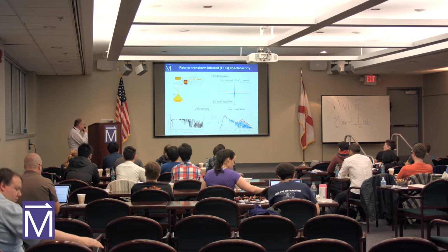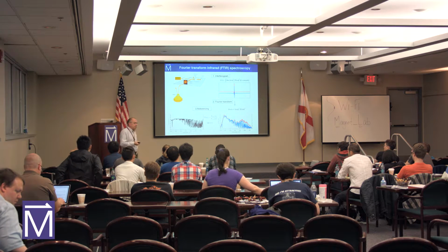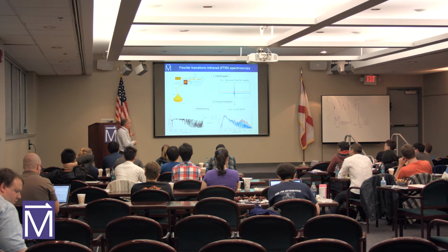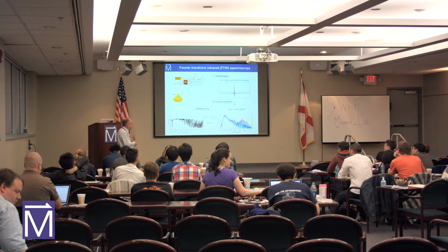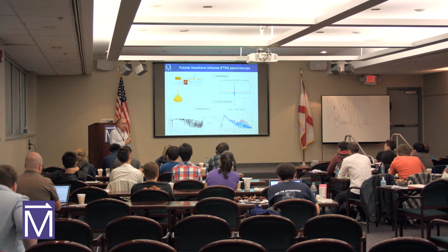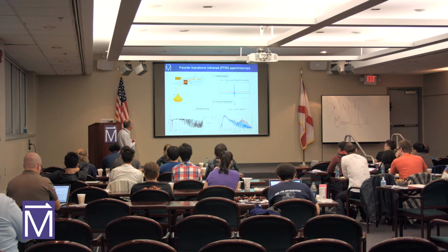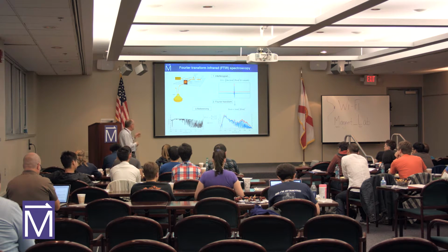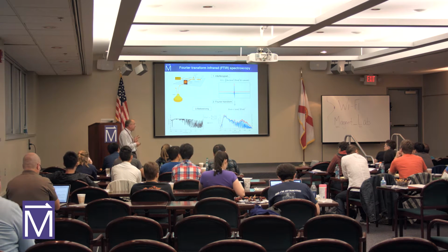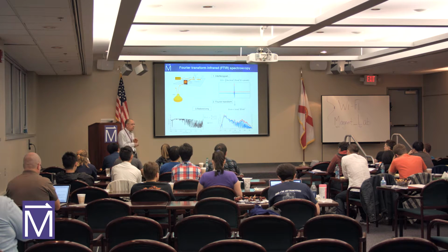Practically, it's not that simple. We use a broadband source. If a single line source produces an infinite sine interferogram, a broadband source ideally produces just a huge spike at the zero path difference. So all the spectral information is in these very tiny wiggles all the way around. We measure first the interferogram without a sample, that's the red line, then put our sample. It's an example, let's say for reflectance measurements, but these graphs are actually absorption spectra of air. Just looking at the interferogram, I can already tell you that we have lots of sharp lines, because we have multiple sinusoidal components.